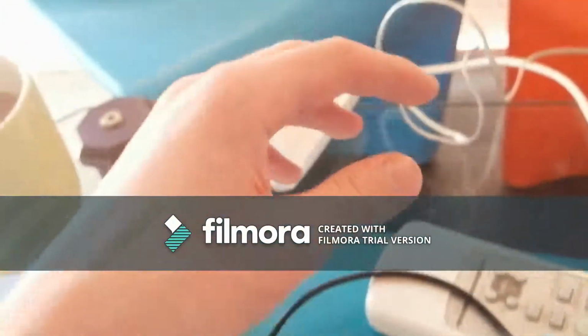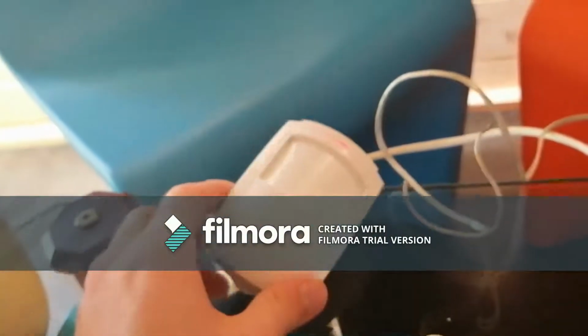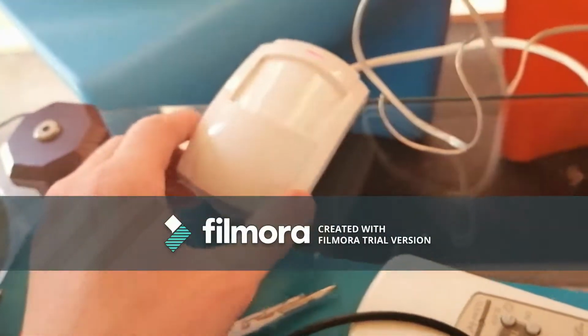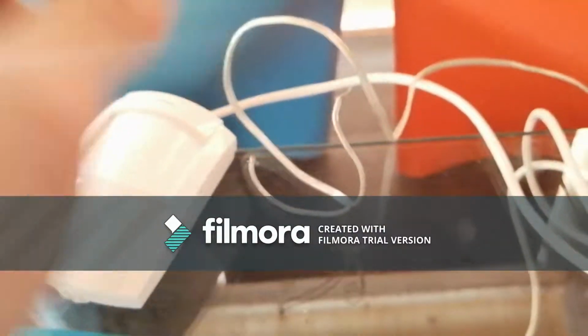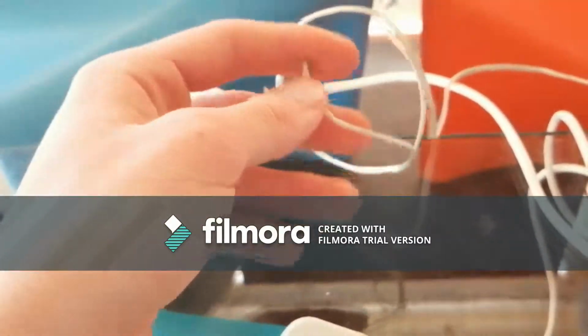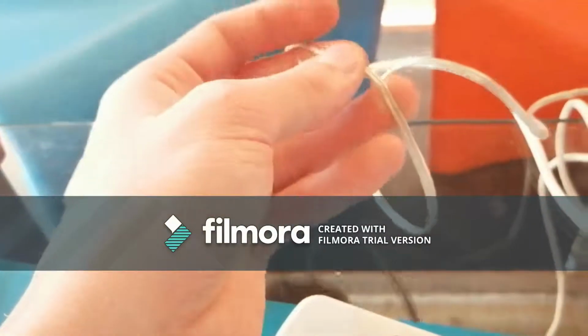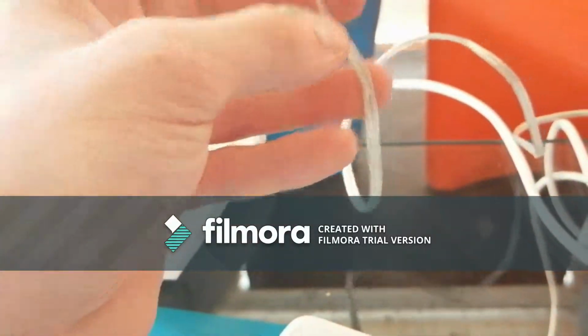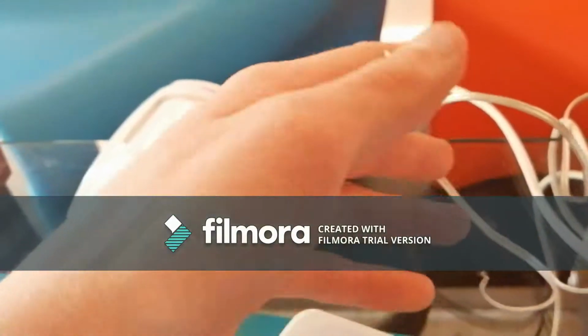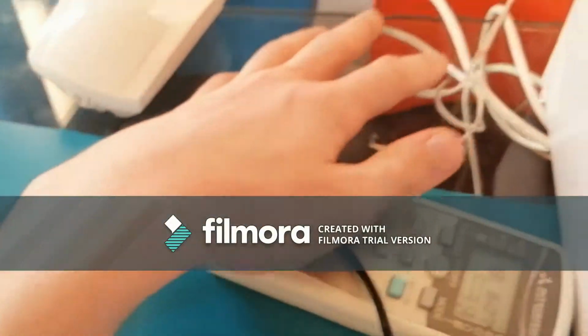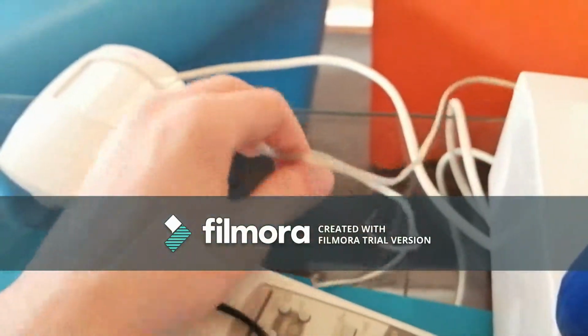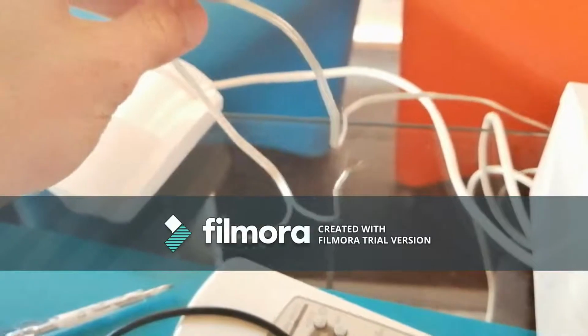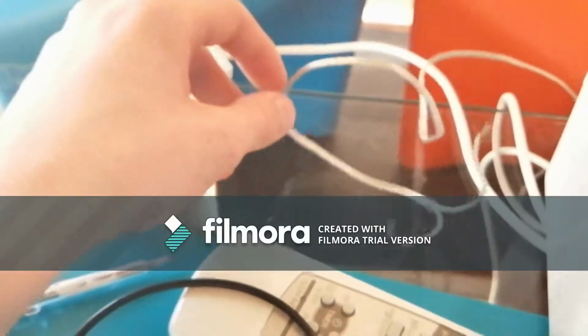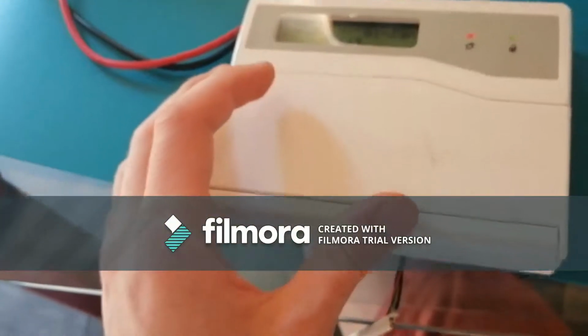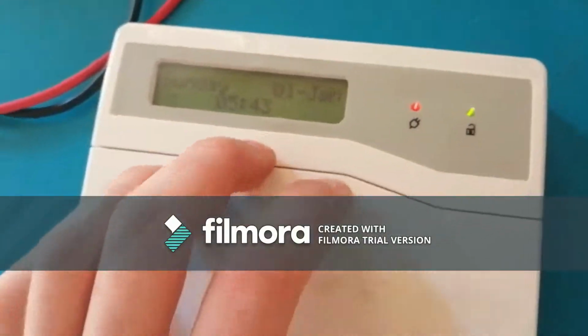Now, as I say, if you were to replace that and the fault still persists, then it is likely to be a cable fault. As I say, the only way to resolve cable faults is to either use spare cores in that cable or just to replace it. But that's a more advanced thing. If that needs to be done, to be honest, it's probably easier getting an alarm company out to sort it.